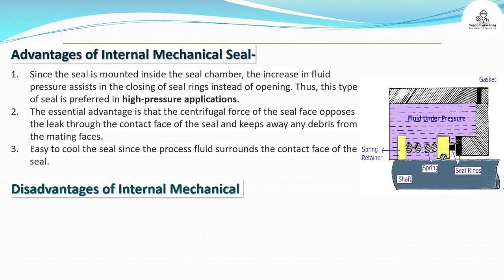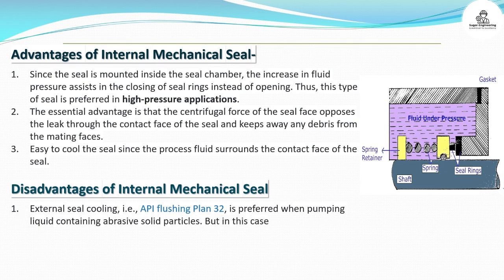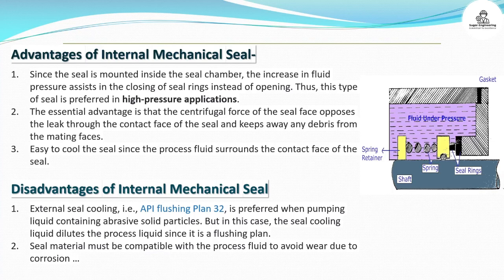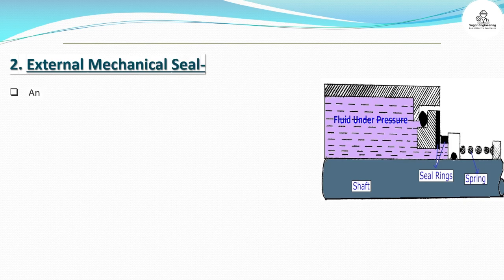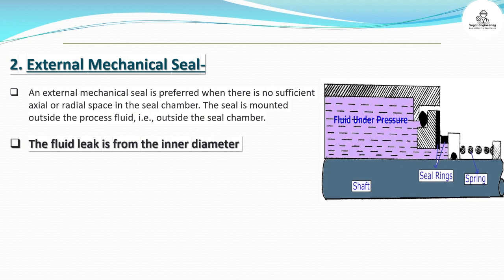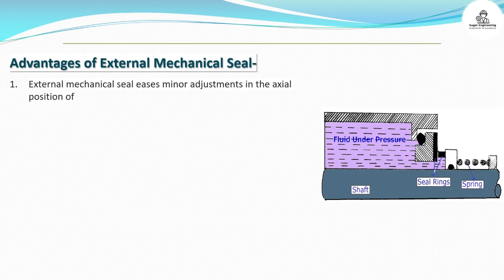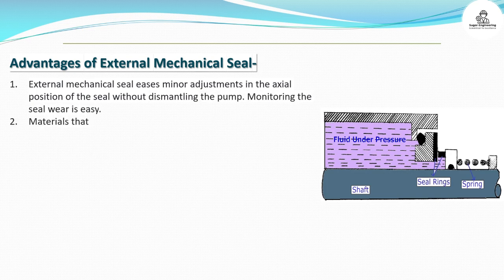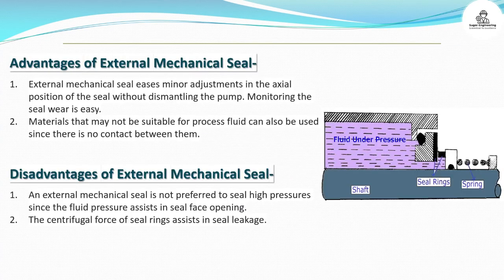Disadvantages of internal mechanical seal: External seal cooling, i.e., API Flushing Plan 32, is preferred when pumping liquid containing abrasive solid particles. However, the seal cooling liquid dilutes the process liquid since it is a flushing plan. Seal material must be compatible with the process fluid to avoid wear due to corrosion. External mechanical seal: An external mechanical seal is preferred when there is no sufficient axial or radial space in the seal chamber. The seal is mounted outside the process fluid, i.e., outside the seal chamber. The fluid leak path is from the inner diameter to the outer diameter of the seal. Advantages: external mechanical seal eases minor adjustments in the axial position of the seal without dismantling the pump; monitoring the seal wear is easy; materials that may not be suitable for process fluid can also be used since there is no contact between them. Disadvantages: an external mechanical seal is not preferred to seal high pressures since the fluid pressure assists in seal face opening.